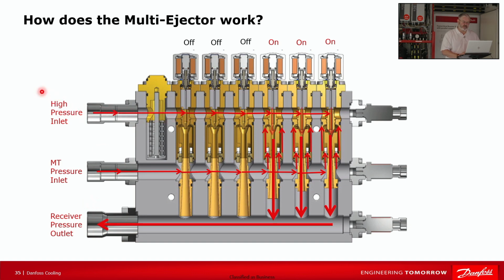So we come to the top. This is coming from the gas cooler. We come here. We restrict the flow. We bottleneck it. That causes a low pressure situation with a Venturi effect that draws in our medium temp return gas. Then they mix together and they exit and they go together down into the flash tank.